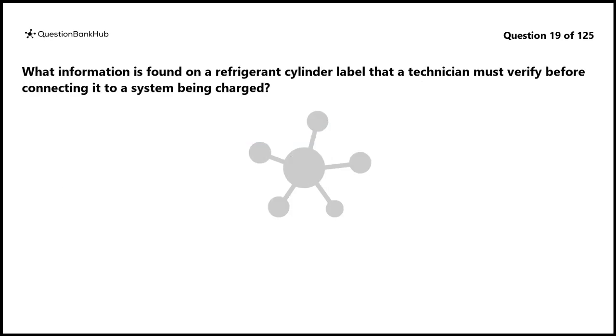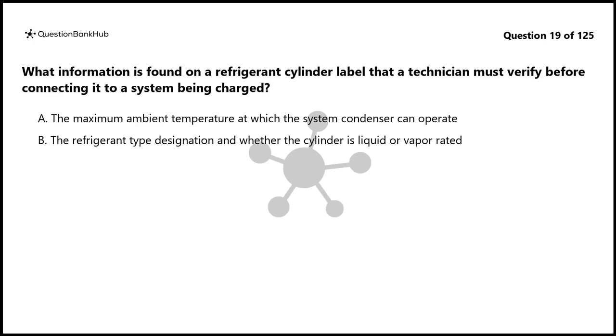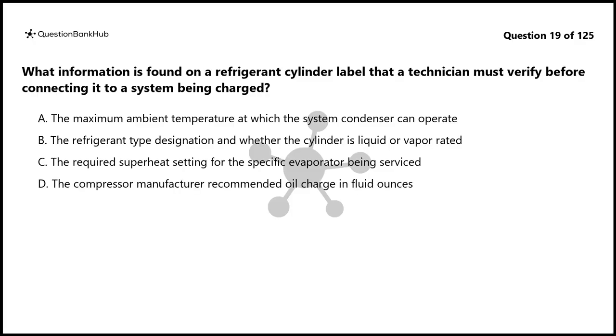Question 19. What information is found on a refrigerant cylinder label that a technician must verify before connecting it to a system being charged? A. The maximum ambient temperature at which the system condenser can operate. B. The refrigerant type designation and whether the cylinder is liquid or vapor rated. C. The required superheat setting for the specific evaporator being serviced. D. The compressor manufacturer recommended oil charge in fluid ounces.